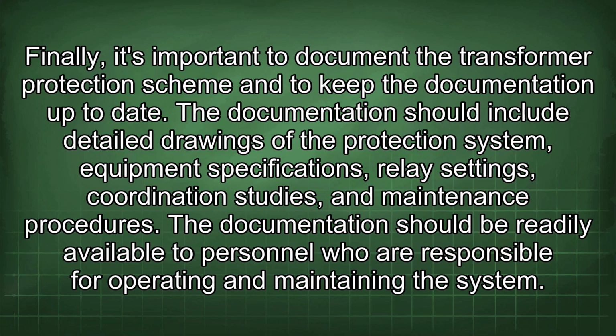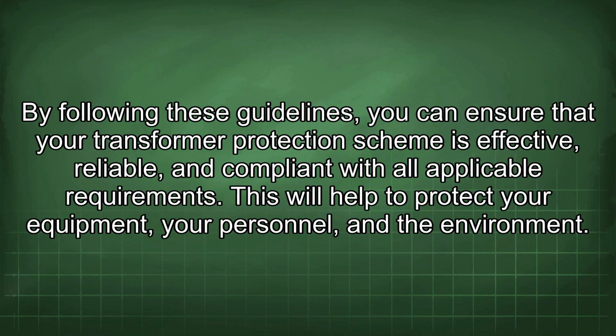Finally, it's important to document the transformer protection scheme and to keep the documentation up to date. The documentation should include detailed drawings of the protection system, equipment specifications, relay settings, coordination studies, and maintenance procedures. The documentation should be readily available to personnel who are responsible for operating and maintaining the system. By following these guidelines, you can ensure that your transformer protection scheme is effective, reliable, and compliant with all applicable requirements. This will help to protect your equipment, your personnel, and the environment.